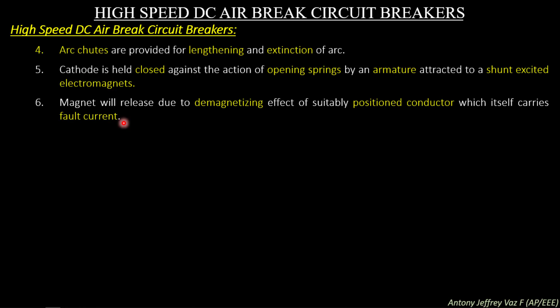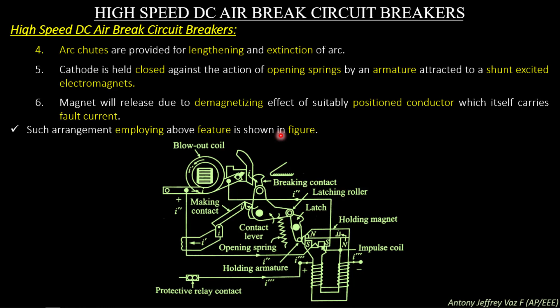The magnet will release due to the demagnetization effect of suitably positioned conductors, which themselves carry the fault current. So the tripping mechanism ensures that when demagnetization of the electromagnet is present, the latch will open and the complete DC circuit breaker will trip immediately when a fault current is sensed. Such an arrangement employing the above features is shown in the below figure. So this is the high speed DC air break circuit breaker.